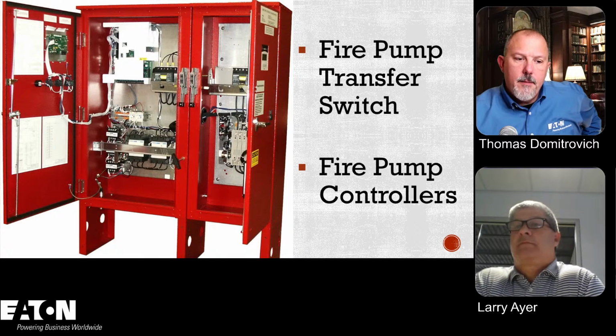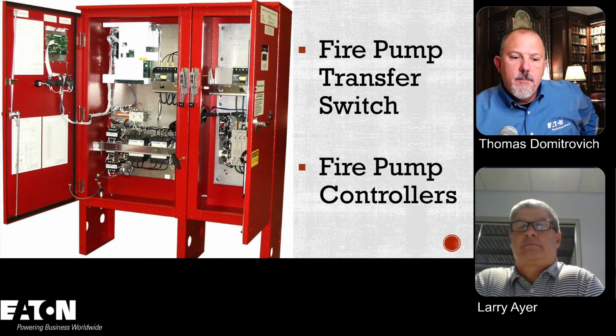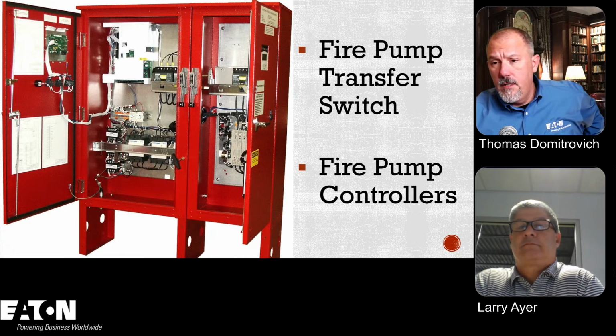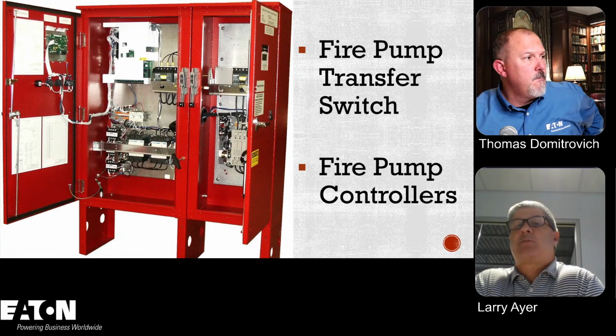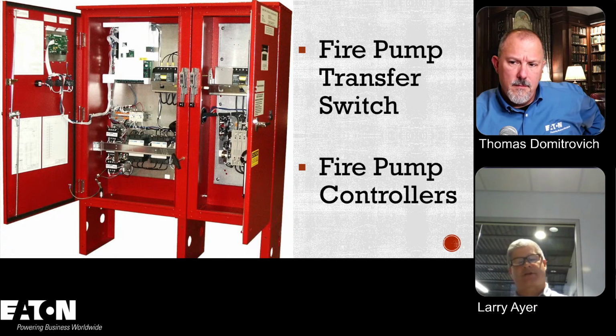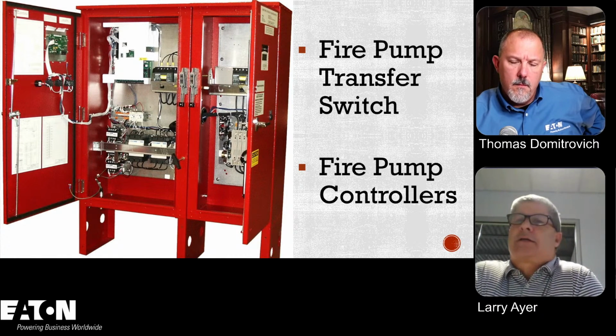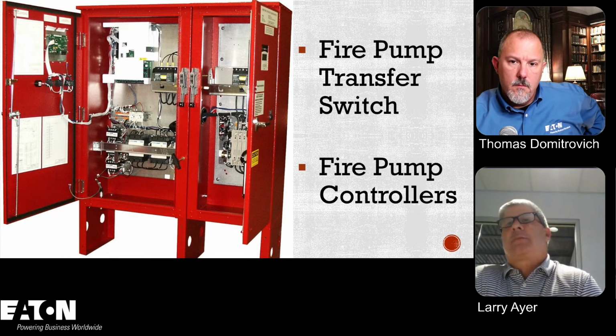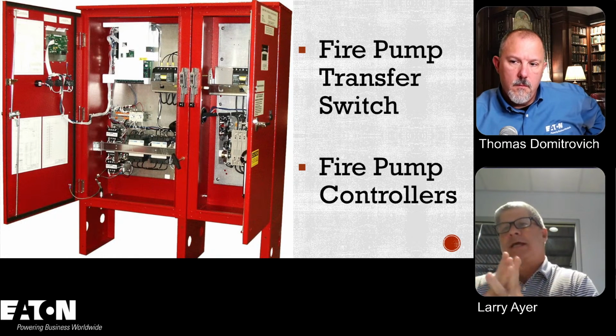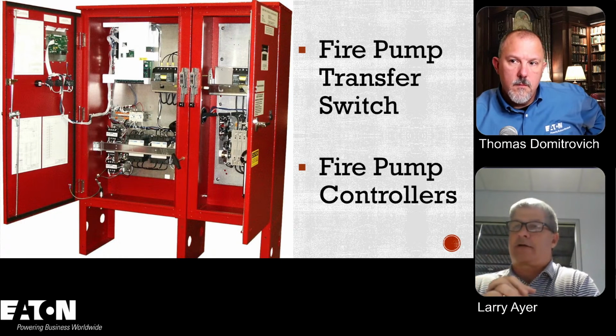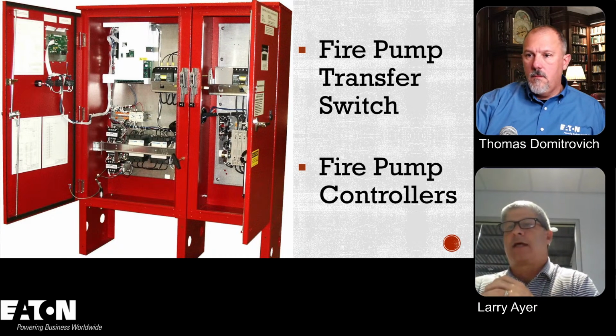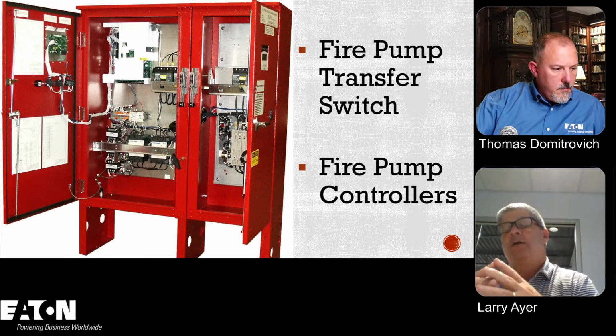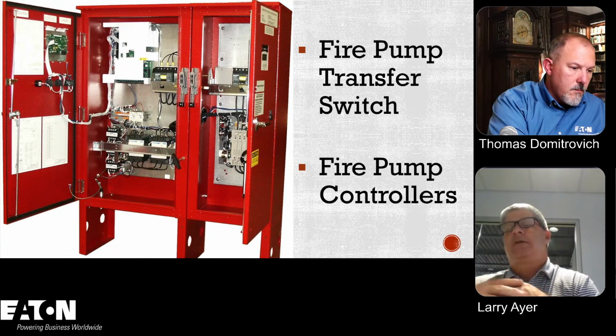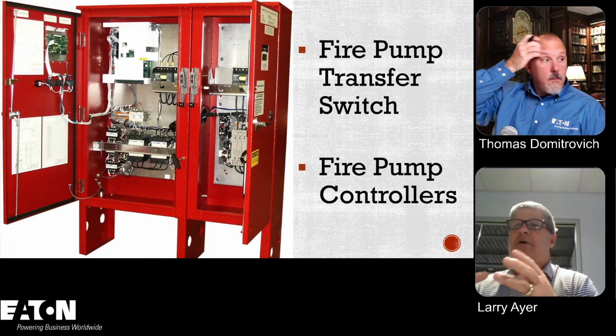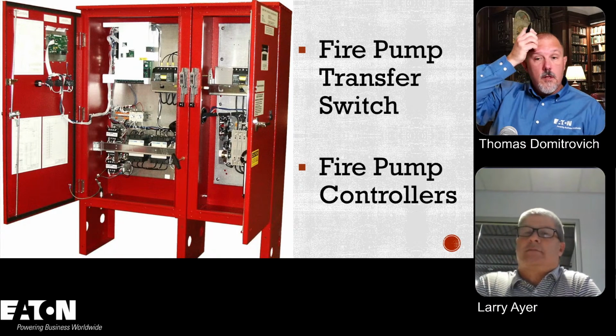Yep. L.A. Markovic asks, is the jockey pump sometimes called the booster pump? I think so, but it's more or less called the jockey pump. I think that's just the jargon in the fire pump industry, and it's well known. When you say booster pump, I think you start to lose what the real intent of it is, which is the maintenance of the pressure. If you're in the fire pump industry, they probably consider that a booster pump as well. But if you're just new to the fire industry or fire pumps, I think jockey pump is probably better jargon.